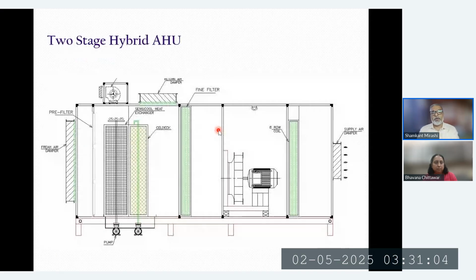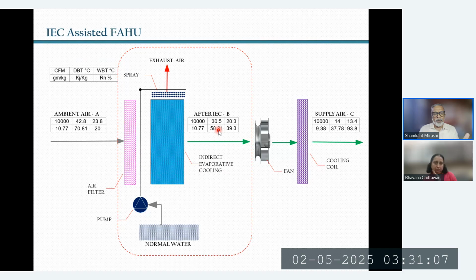So we have seen and we have deployed systems where the power consumption is reduced by almost 30%. We have a system installed here in Pune. We were lucky enough to be involved at the design stage with a consultant. The original design of the system was almost 300 ton. This was installed sometime in 2019-20. By our intervention, and thanks to the consultant being open enough to look at these suggestions, the original 300-ton load was delivered with a 200-ton system. So 100 ton avoided on day one. And it has been working from sometime in 2019-20 all the way to today.